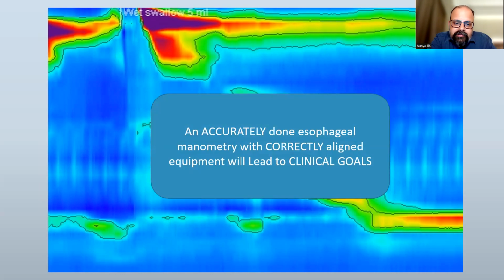Now, the most important thing that I usually tell to all my students and all my fellows is that an accurately done esophageal manometry with correctly aligned equipment will lead to clinical goals. What does it mean? It tells you that to do an accurate esophageal manometry, and for that matter any manometry, maybe rectal, maybe anything else, you need correctly aligned equipment. And only then you'll actually end up having good clinical goals. So the important point you have to learn is the correctly aligned one. That means that your equipment has to be standardized and calibrated as per the manufacturer. You have to troubleshoot along the way, and only then will you have meaningful tests and recordings done.